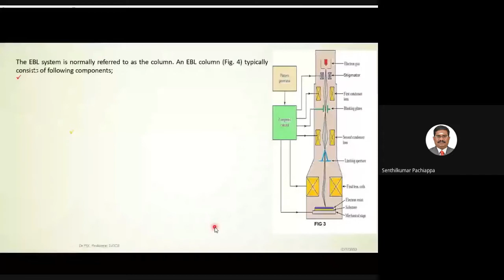The electron beam apparatus is normally referred to as an electron beam column. It typically consists of the following components. The electron source: electrons may be emitted from a conducting material either by heating or by applying an electric field. Here is the electron gun. Stigmators: a stigmator is a special type of lens used for alignment of the e-beam. Stigmators may be either electrostatic or magnetic and consist of 4 or more poles.